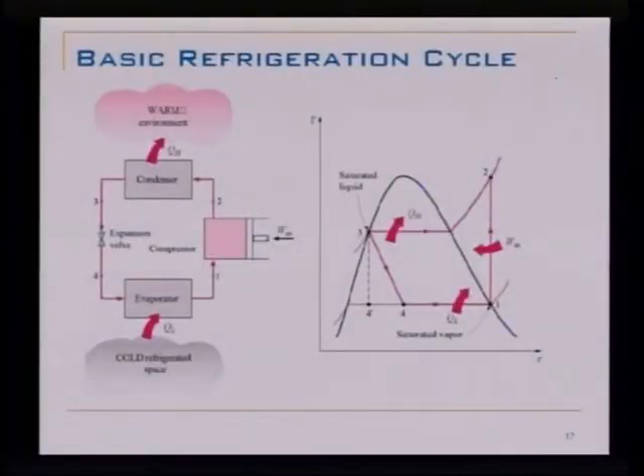So sorry again, this is where it gets a little bit deep, but it helps to go over and remember a few things. Refrigeration systems are all about boiling and condensing that refrigerant. That's how the magic of a refrigeration cycle happens. The compressor takes the cold gas, pressurizes it, and makes it very hot. That goes up to the condenser and cools off and turns back into a liquid, and that's what gives up all the heat, throws the heat away to the outside. The refrigerant then goes through an expansion valve, the temperature drops, and it goes into the evaporator where it essentially boils back to a gas and sucks up all the heat from the refrigerated case. And the compressor is just the pump that pumps it around and the phase change is where all the heat happens.